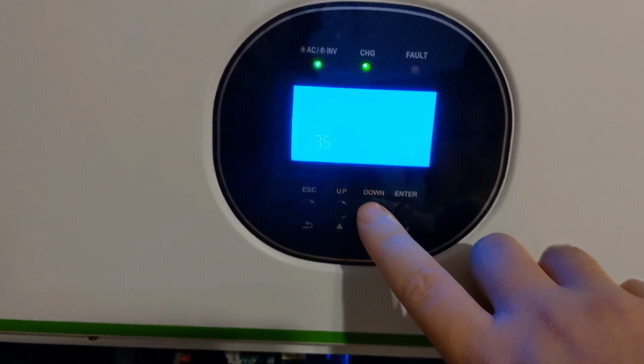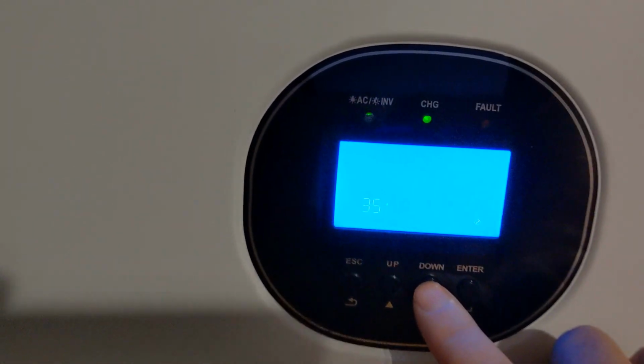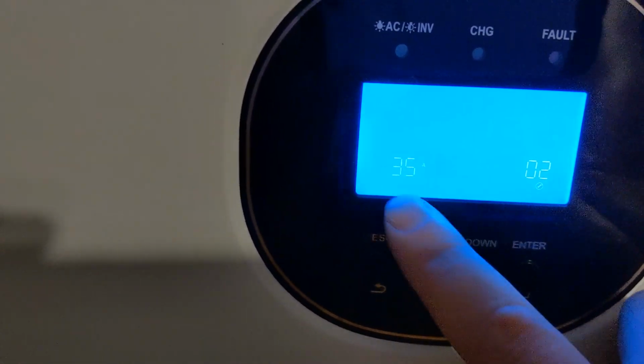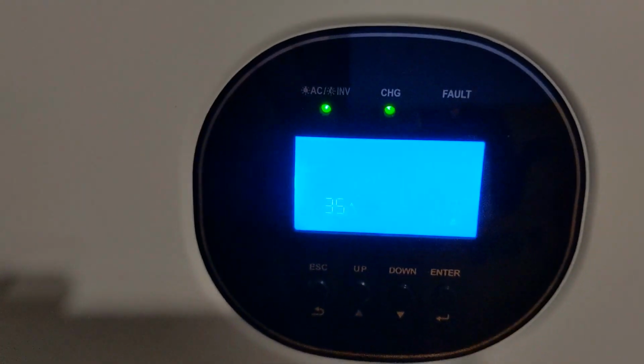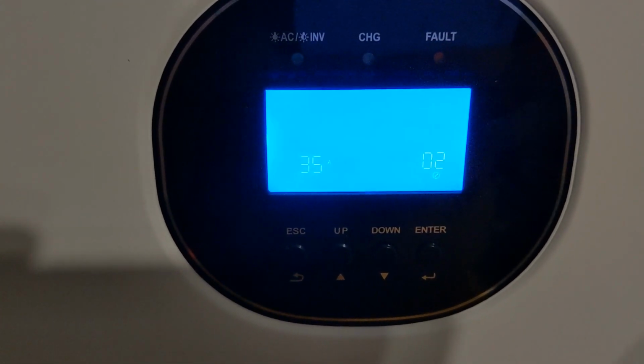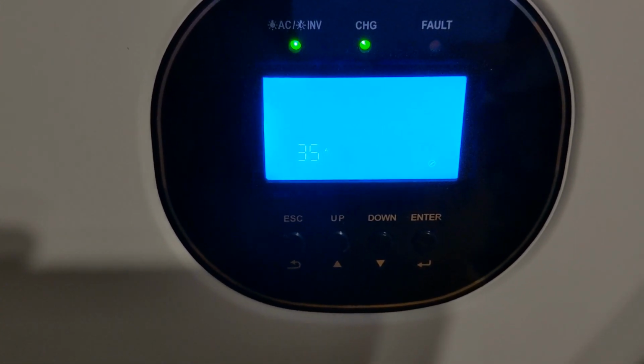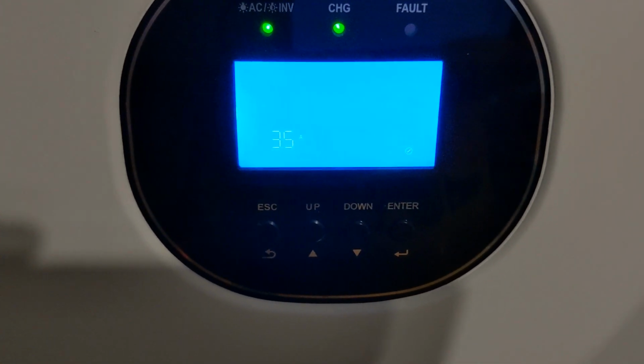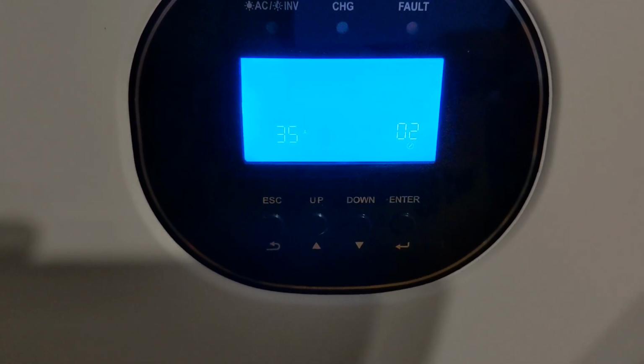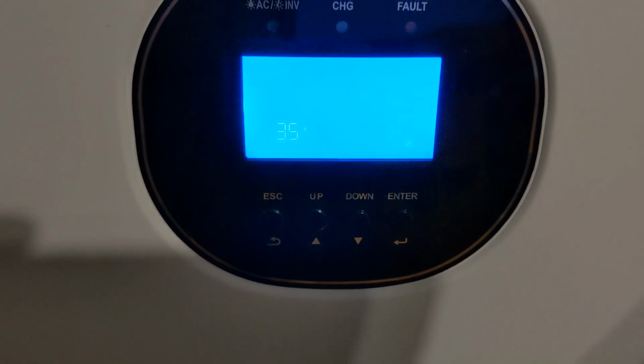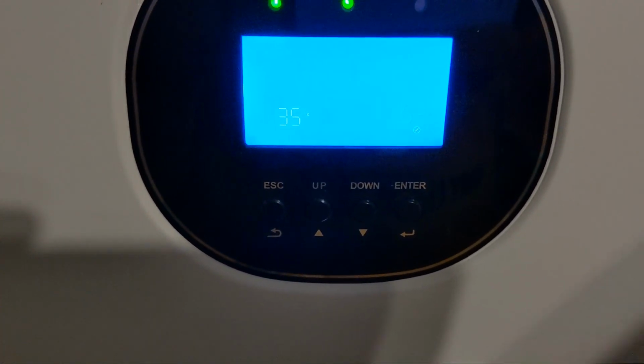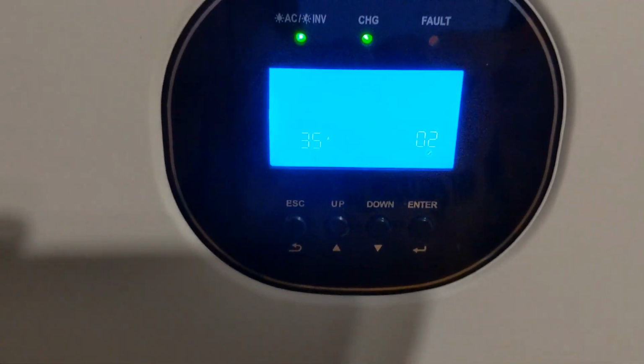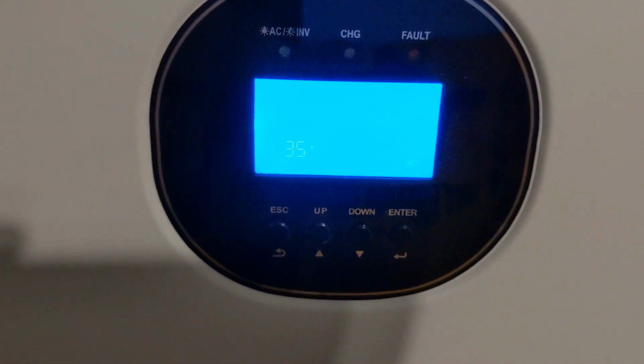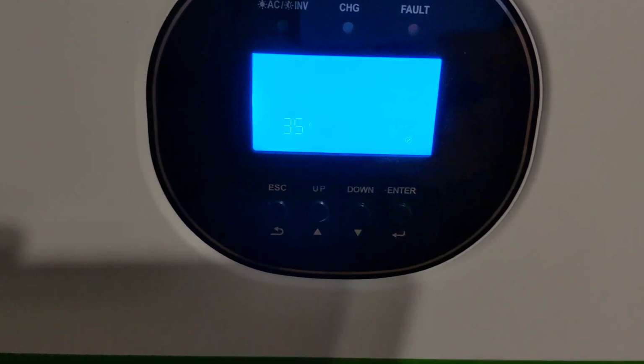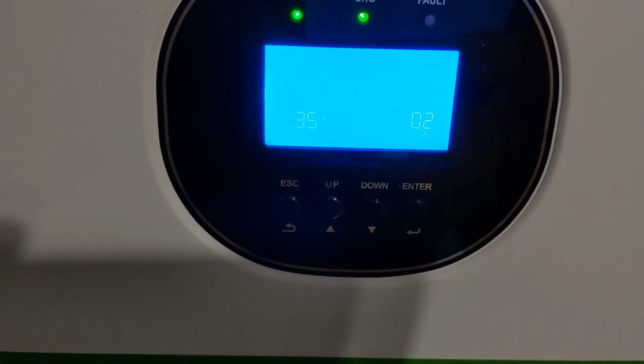Going down through there, you've got your ability to set your limit for the amount of charge. I'll grab this little booklet so I can remember some of these things. Hold on. So this guy here, this allows you to basically set the maximum amount of amperage you want the charger to put in. This combines both the utility charger as well as the solar. So there are certain modes that you can put this in where it'll charge the batteries from both your solar and your utility. So this is the total number of both of those sources combined.